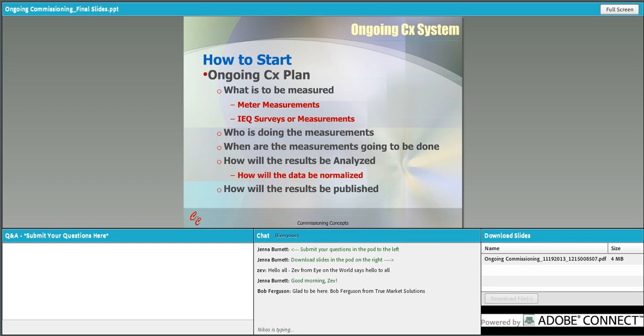So how do you get started? First of all, you have to create a commissioning plan. You have to figure out what you're going to do. So you have to figure out what you're going to measure, who is going to do the measurements, when the measurements are going to be done, how the results will be analyzed, and how you will publish the results. Now, normally measurements depend on the type of system you have to gather data, but normally measurements start with utility bills. That's actually a meter measurement. That's the easy one to do, or you might have submeters that you have to physically measure or gather measurement data from. Now, IEQ is much more difficult.